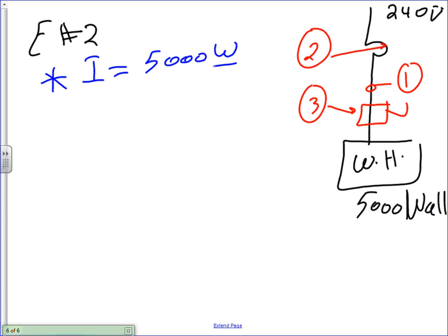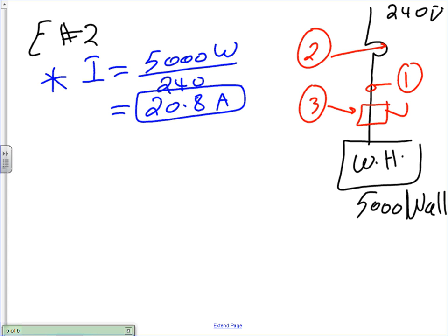5000 W divided by what's the voltage? 240. I need 2 gentlemen to agree on one answer. 20.83. Thank you. 20.8 amps. We size things based on amps. Find the full load current of this water heater first. We need to find the full load current of this water heater.